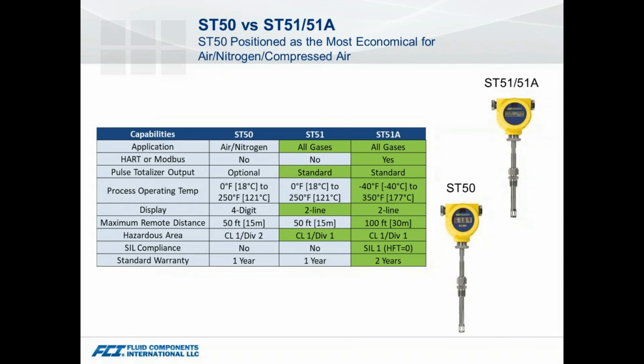So here is a more generic comparison of the different flavors of FCI meters. Again, the ST50 is the low end side of it. The ST51 gives you a little bit more capability. With the ST50, the calibrations are air and nitrogen, and it's a Class 1 Div 2 device. As we step up to the ST51, we can do all gases, and that gets into biogas and hydrocarbon mixtures. We get the 2-line, we get the Div 1 rating, so now we're into the explosion-proof enclosure ratings all the way around.